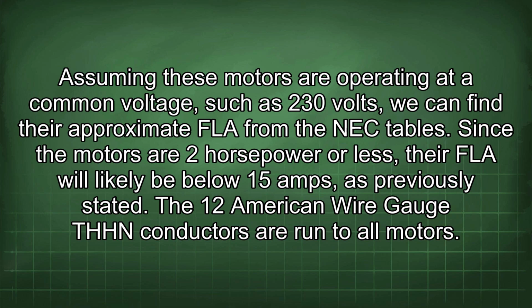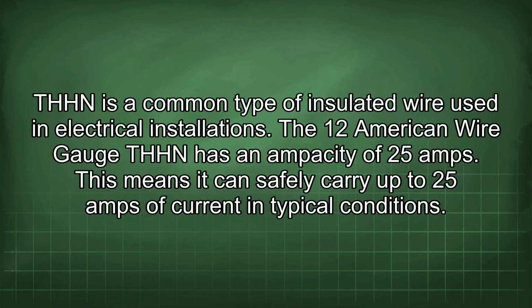The 12 American wire gauge THHN conductors are run to all motors. THHN is a common type of insulated wire used in electrical installations. The 12 American wire gauge THHN has an ampacity of 25 amps. This means it can safely carry up to 25 amps of current in typical conditions.